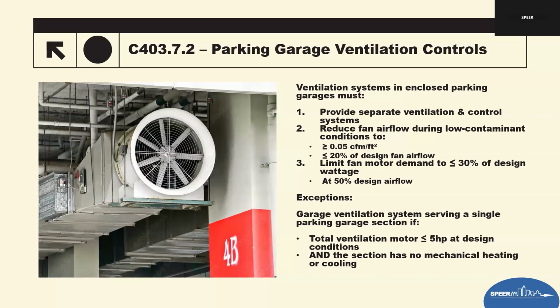Field inspections. Observe the fan's operation during low load conditions. Confirm VFD operation and minimum fan speeds. And then check sensor placement and calibration. And then verify the total motor horsepower if the exception is being claimed. It's got to be 5 horsepower or less. That way it can be exempt.